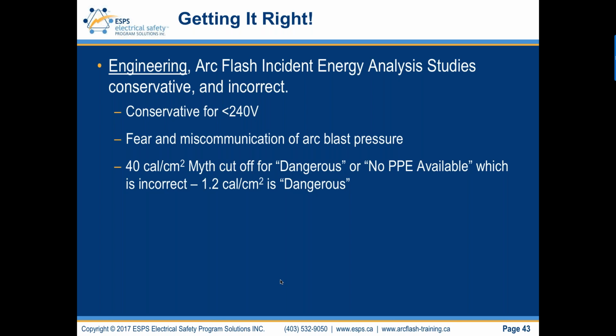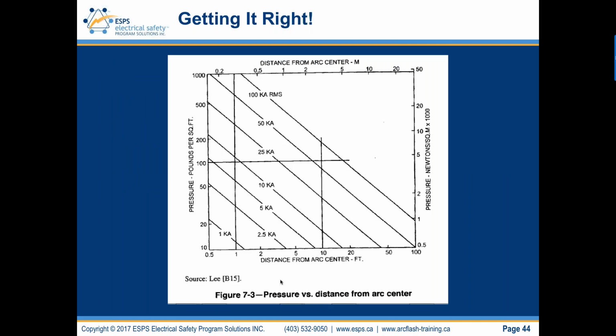And I think some engineers will still report out that 40 calories is dangerous, 40.1 calories. It's not a true statement and it's not dangerous. And there is PPE available. Oberon Company makes arc flash suits up to 140 calories arc thermal performance value. The blast pressure is not the problem that it's been made out to be. All right, so again, if you want more information on that, let me know.